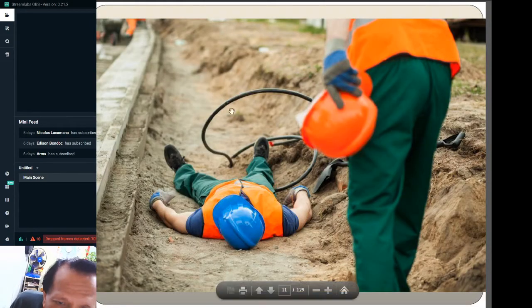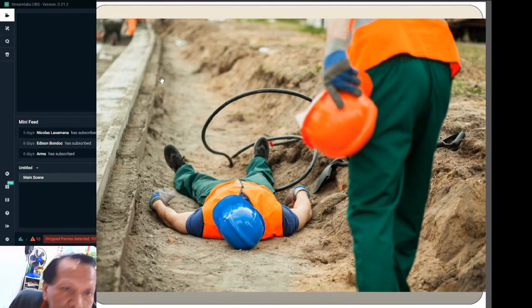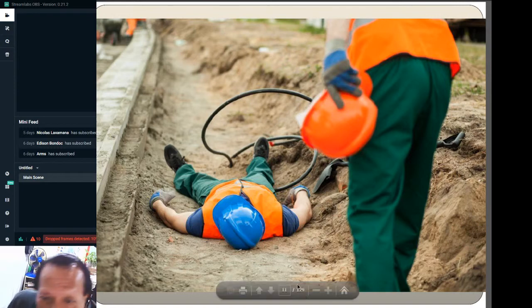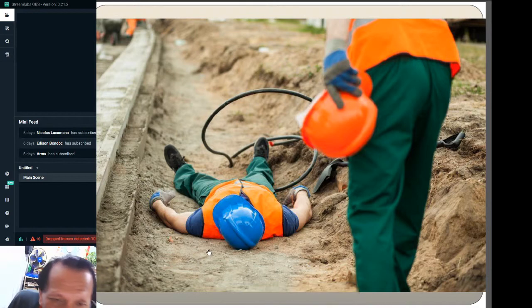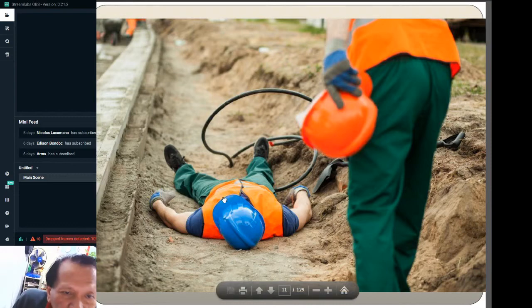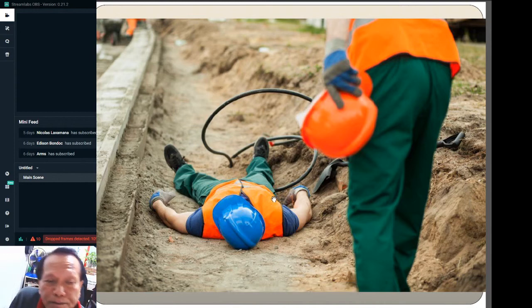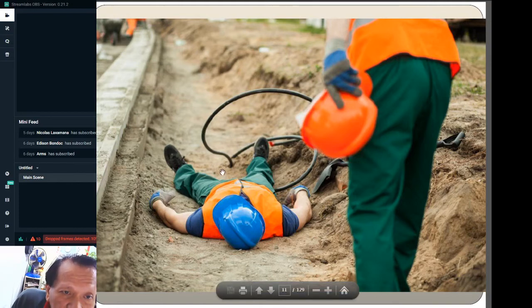See, this is another picture. We took it from the internet, showing that this guy would be digging, struck a cable which might have damaged the insulation of the cable and got him electrocuted. Okay, so we must be careful when we are digging outside. We should be very careful. We should get the plans, refer to the old plans, as-built plans, so that we would know if there are lines, or if not, we should use detectors to find out if there are lines traveling underneath the location of your excavation.